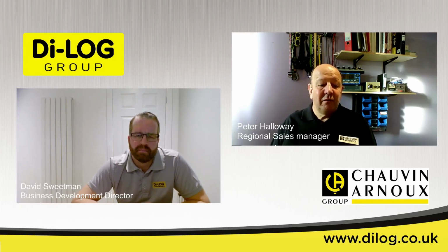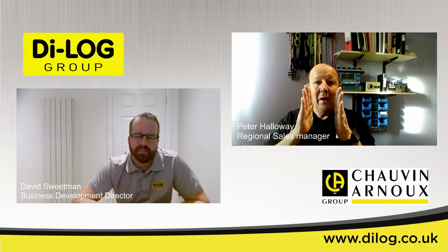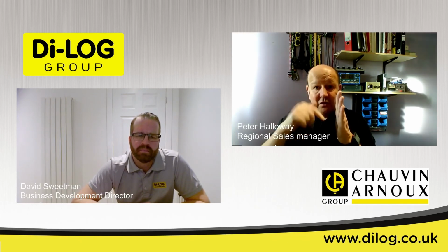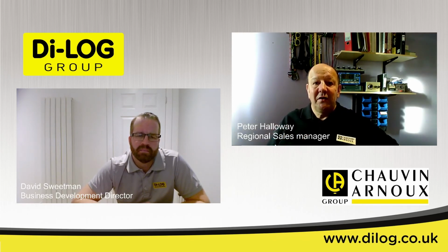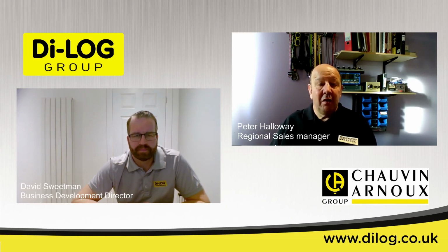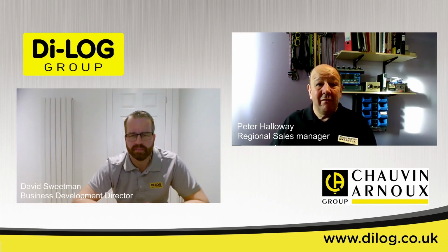Now, the capacitors themselves - think of them as two parallel plates with a substance between them, known as the dielectric. It could be air, it could be something else, but typically that will degrade over time. Speaking to power factor correction manufacturers, some of them will tell you it could degrade every 3 years.